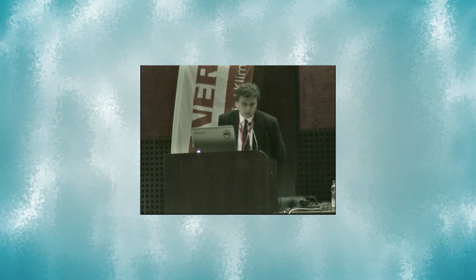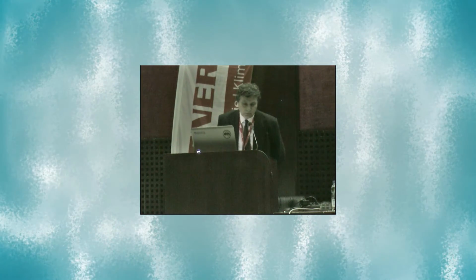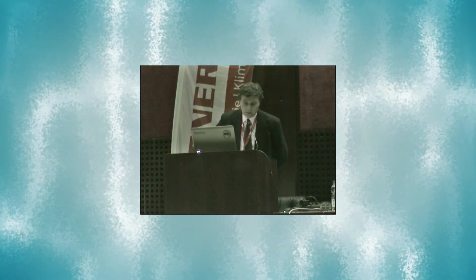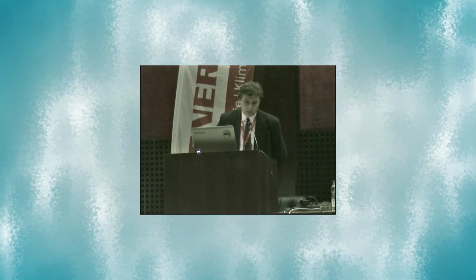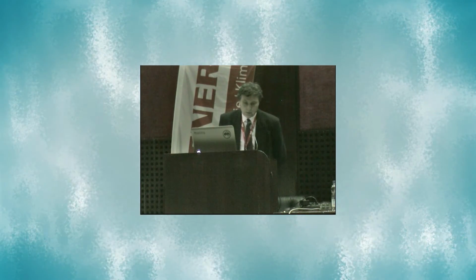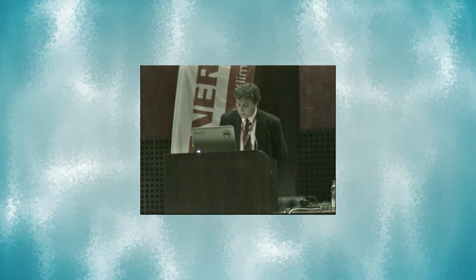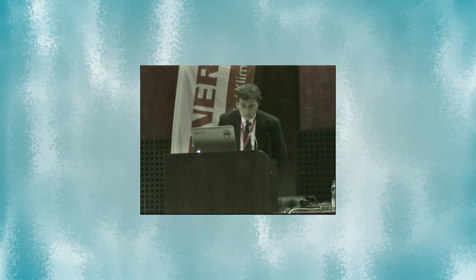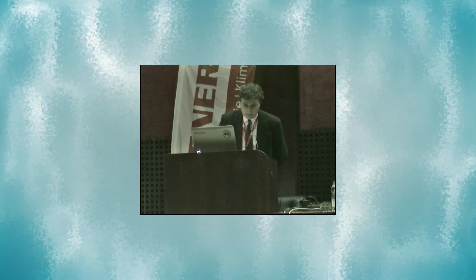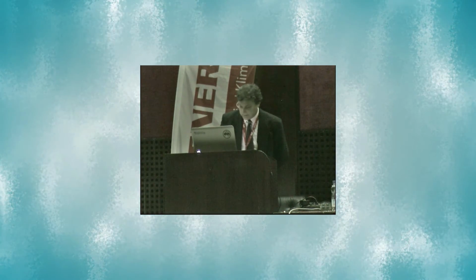The 30 centimeters of very thick insulation at the roof was doing nothing, because through this hole of 15 square meters, the temperature outside was nearly equal to the temperature in the roof void, negating the purpose of the roof. Outside air was ducted with a common duct to all the units, so that wasn't needed. Why that was designed and implemented that way is a question for the designer.